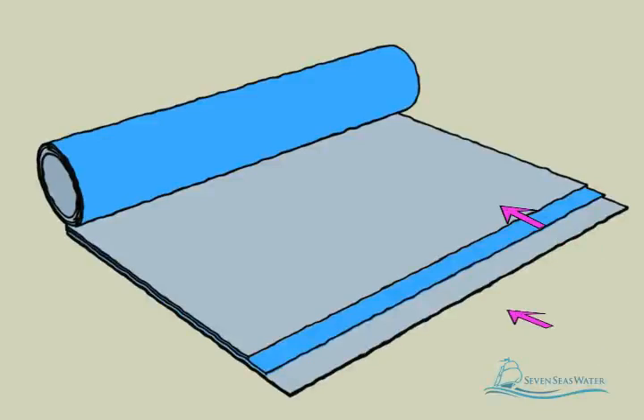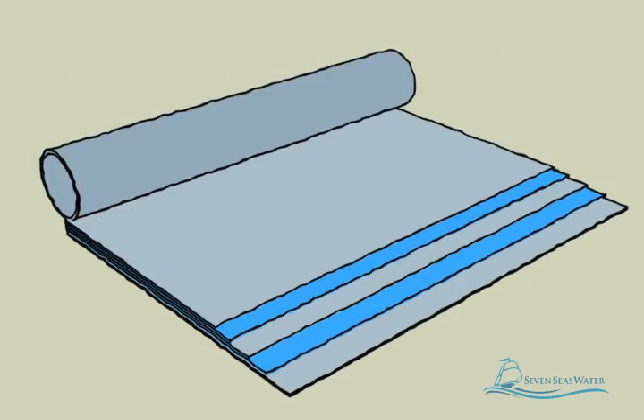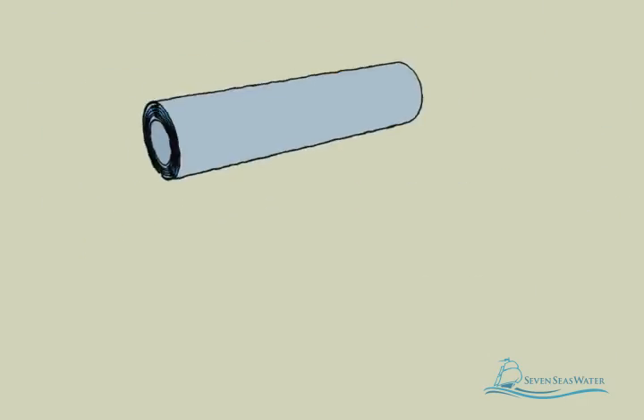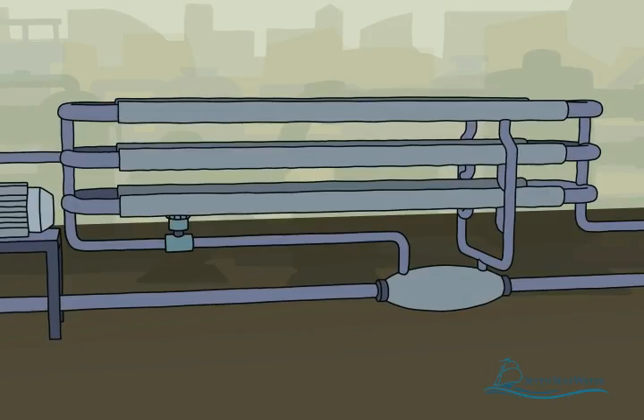The reverse osmosis membrane can be thought of as a number of sealed envelopes connected at their open ends to a tube. There are spacers between each envelope which allow water to flow across the membranes. The membrane envelopes and spacers are then wound around the tube like a roll of paper towels. The reverse osmosis membranes are then enclosed in a fiberglass shell.